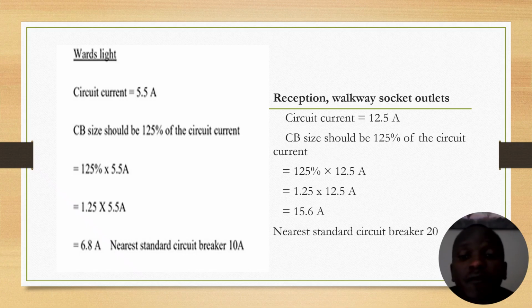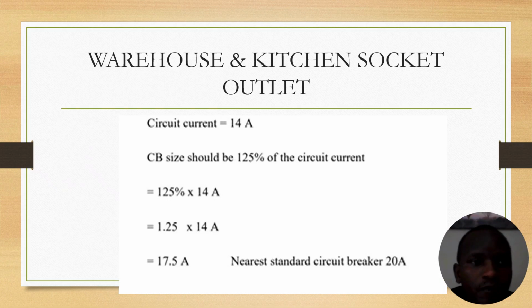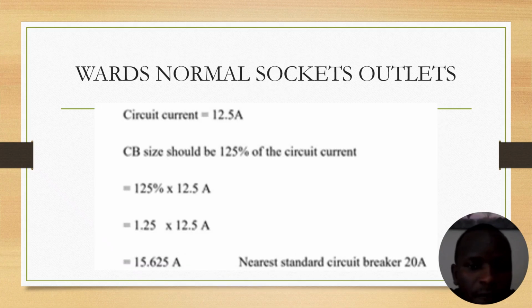This is the standard which you must follow so that there won't be any tripping of the circuit breakers. We are avoiding the tripping of the circuit breakers by overloading on the sockets. For the warehouse and the kitchen socket outlets, the circuit current is 14 amps, then we're going to multiply by 1.25, then it's 17.5 amps, and the nearest standard breaker will be 20 amps. This is to ensure safety on the breaker and the load, so that it must not be overloaded. It can take the amperage.